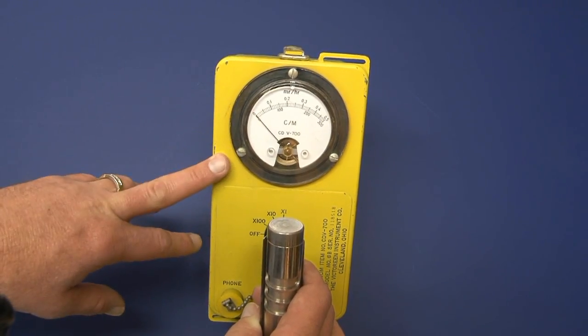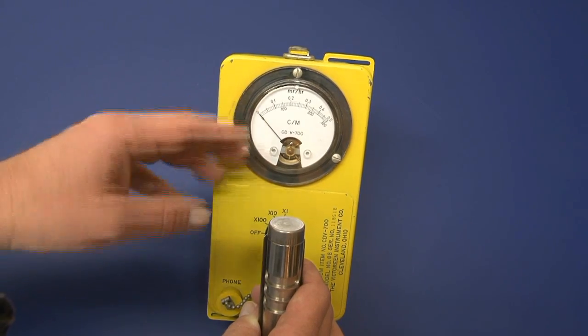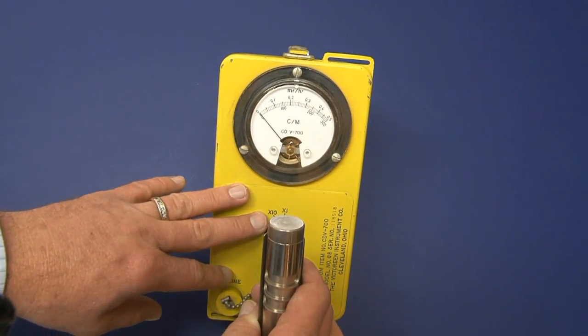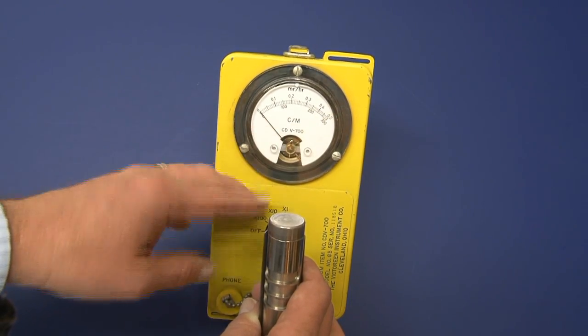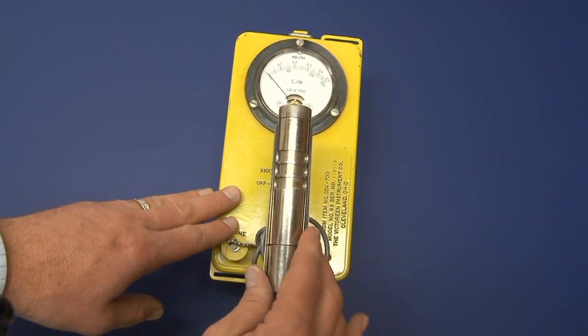To avoid that problem, a lot of the modern survey instruments that are out there, if they exceed the capability of the instrument, they'll peg high and stay high. The needle won't fall back down to zero.